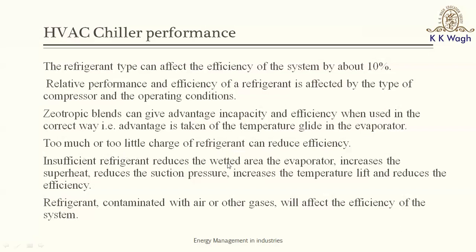Insufficient quantity of refrigerant reduces the wetted area of the evaporator, and you understand that that would decrease the heat transfer, and it would increase the superheat. Superheat is basically the temperature difference between the entry of the refrigerant into the compressor and the temperature at the outlet of the evaporator. So if this degree of superheat increases, that would reduce the performance of the system. That would reduce the suction pressure, and it would increase the temperature lift, and that would also decrease the coefficient of performance. And then one needs to understand that the refrigerant has to be maintained clean.